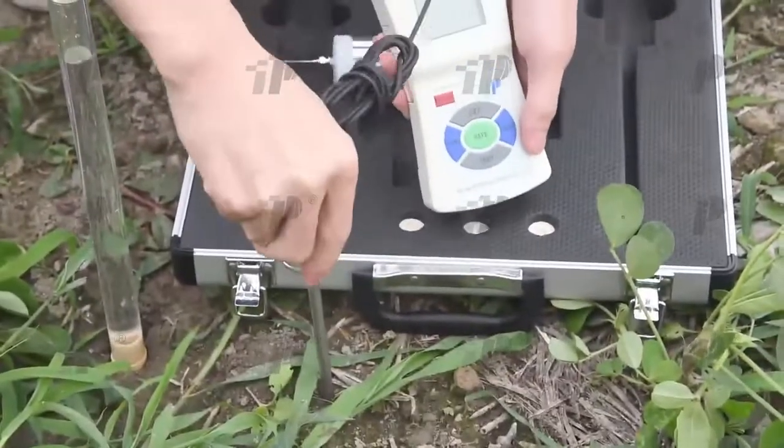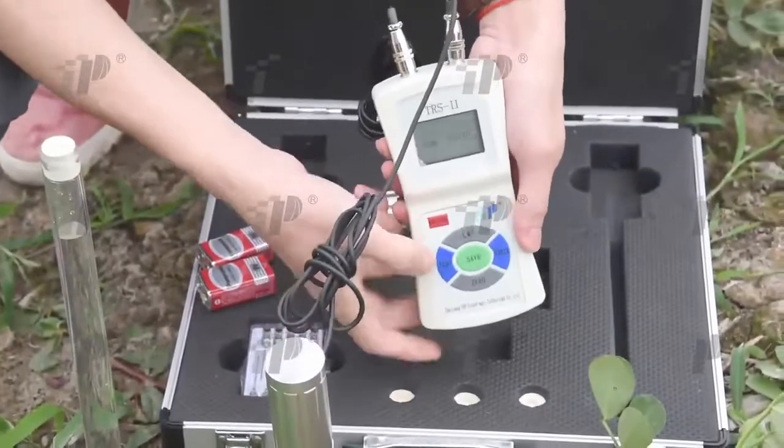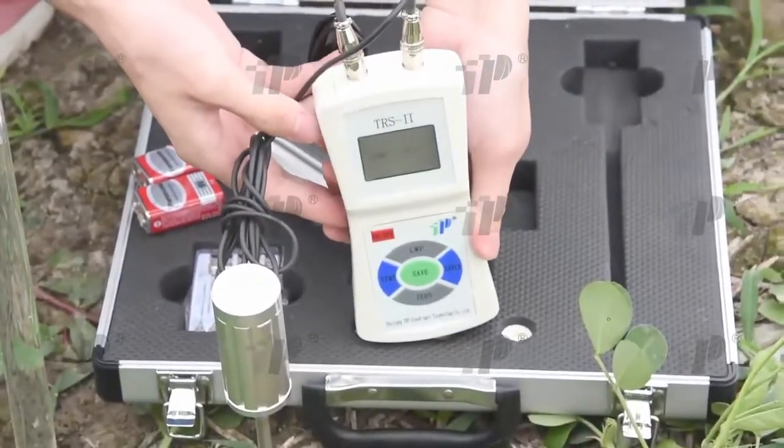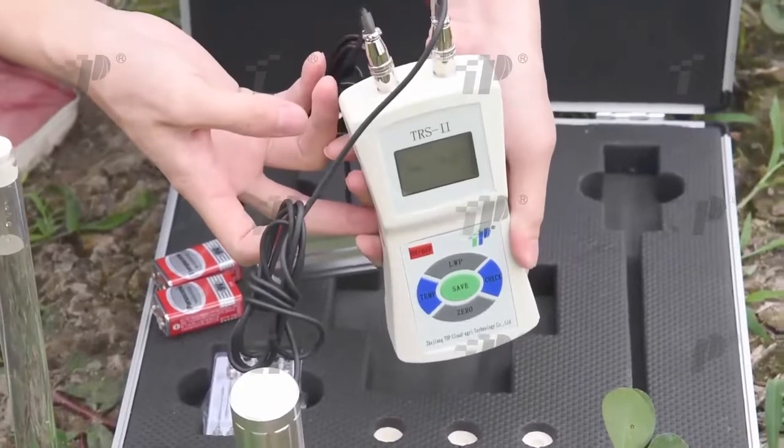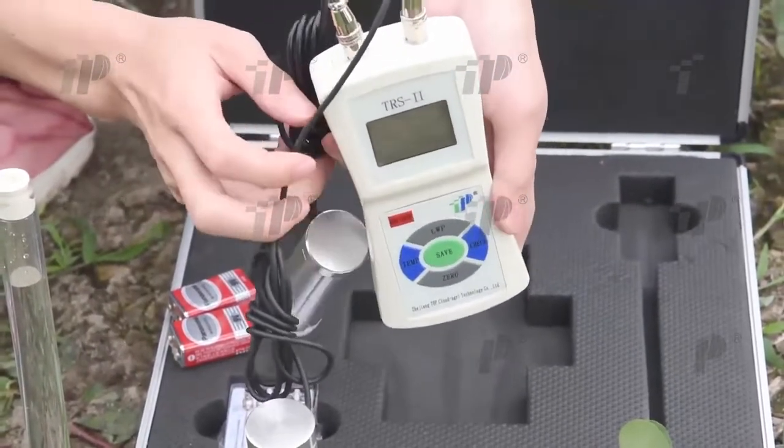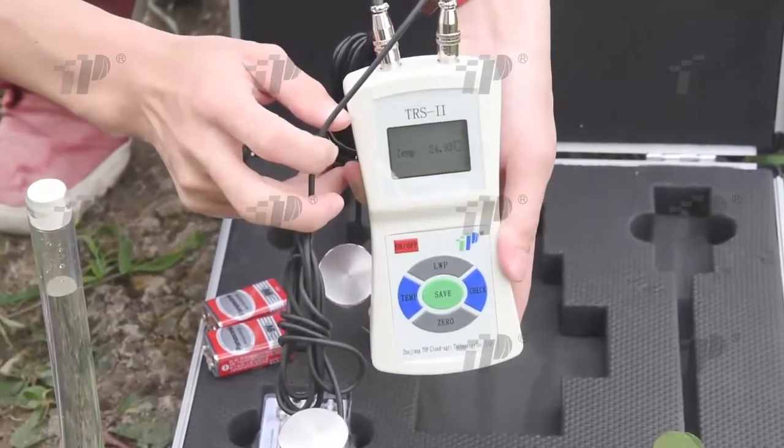Now, let's do the temperature testing. During testing, insert the aviation socket of the temperature sensor to the upper right socket of the displayer. Then turn on the power switch, click the temp button, and insert the top of the temperature sensor to the place which needs temperature measurement.